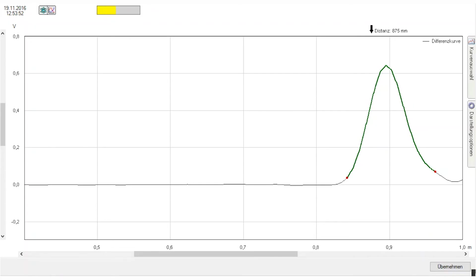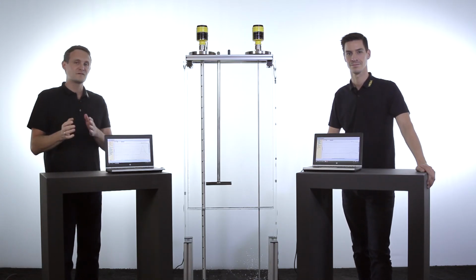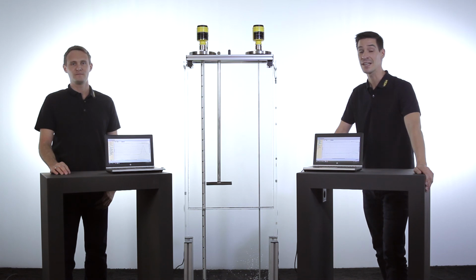And we can see here, there is no influence at all for the coaxial probe. The reason is that the whole measurement is done inside the tube, so that installations left or right of the probe have no influence at all. No matter if tank installations or media which are difficult to measure.